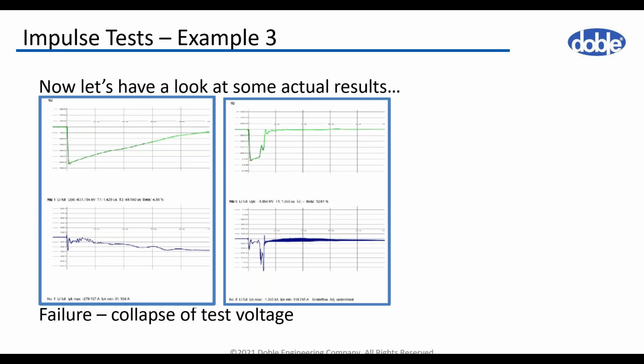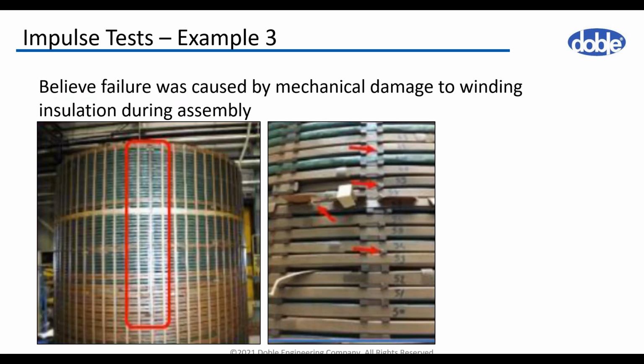This is, let's say, a good case in order to demonstrate a problem, but in other cases, the failures are not that visible on the oscillogram, and a very careful look at this diagram should be taken. So this is how the problem looked after the transformer was taken out of the tank and the windings were disassembled. We found multiple failure locations within a particular area of the winding, and it was believed that the failure was caused by mechanical damage during assembly.